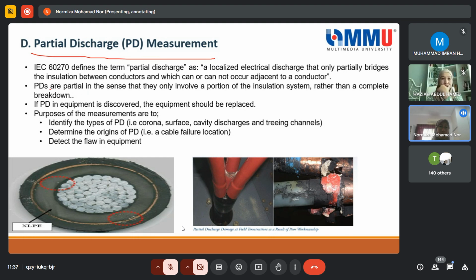So here PD is partial discharge. It means that only part of the insulation has a void or a flaw. In some cases under high voltage, this can easily become faulty, or it may not be faulty. Only after some time or only after very high voltage, it can cause a fault in the system. But in general, as the term itself says, it is partial, in other words, only part of the insulation is breached, or has a flaw.